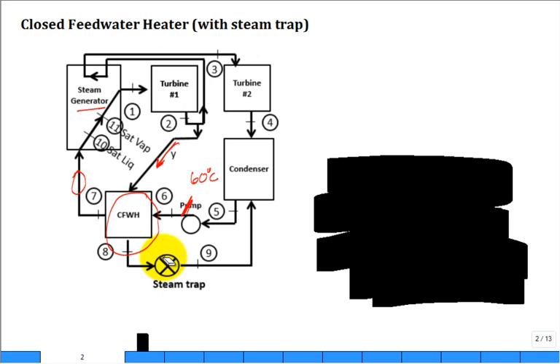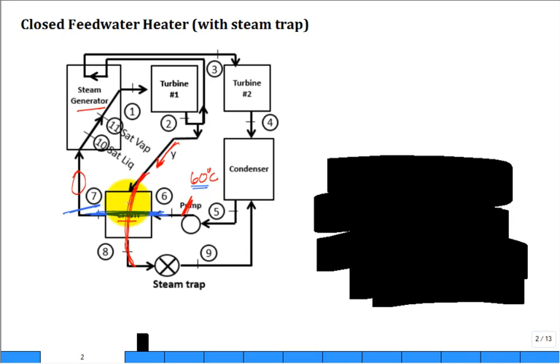In a closed feed water heater, the fluids don't mix. There's a hot fluid stream (drawn in red) that continues through the heat exchanger, and a colder fluid stream that gains heat — going in at maybe 60°C and coming out warmer at state 7. Heat transfers from the hot stream to the cold stream. There are two inlets and two outlets. The hot-side fluid must be returned to the cycle — not lost to the environment — so it's passed through a steam trap and dumped into the condenser.